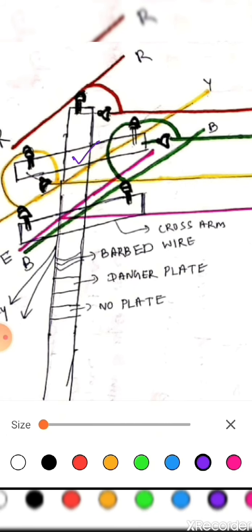And this is the existing cross arm. This is the existing cross arm. Here we have connected the new cross arm, so the quantity is 1 number. Next is HT 11 kV disc insulator with fitting.